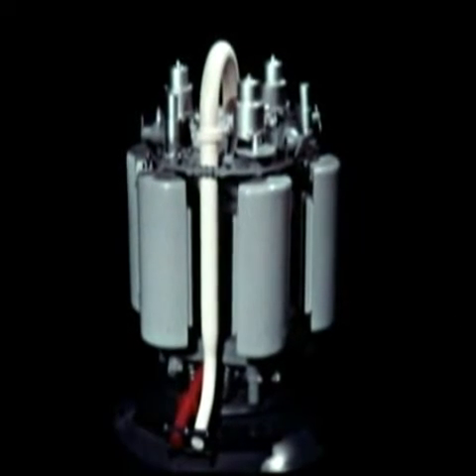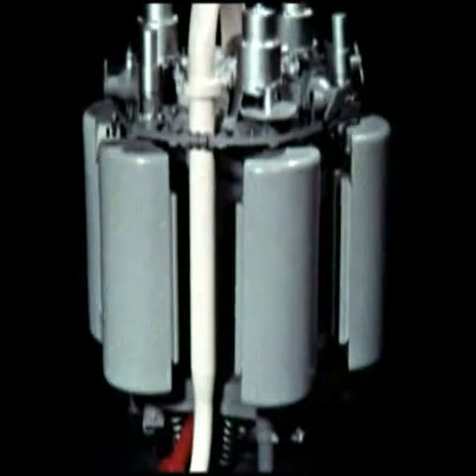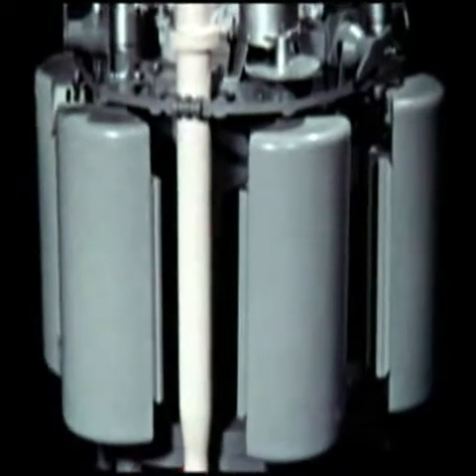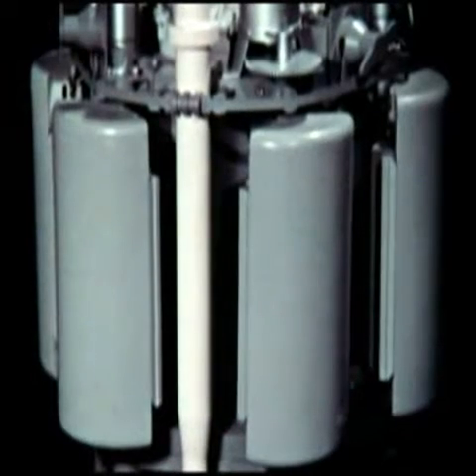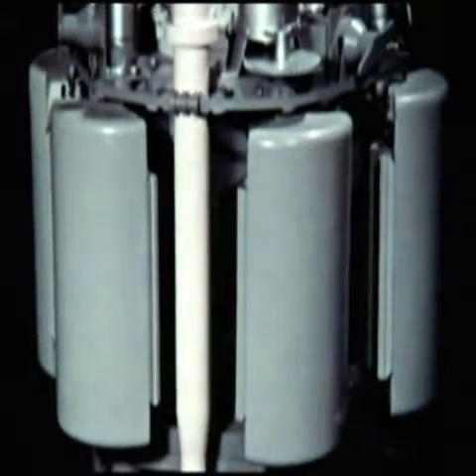The reactor is designed for a NaK coolant outlet temperature of 1300 degrees Fahrenheit with a controlled dead band of approximately plus or minus 20 degrees Fahrenheit and a coolant inlet temperature of 1100 degrees Fahrenheit. During rated power operation, the NaK coolant flow rate is approximately 13 pounds per second with a pressure drop of less than 10 psi through the nuclear system.